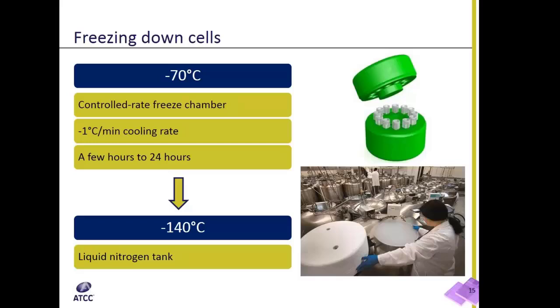The length of time needed in the minus 70 would depend on the type of chamber used. After spending some time at minus 70, usually a few hours to 24 hours, the vials must be transferred to minus 140 degrees Celsius for long-term storage.